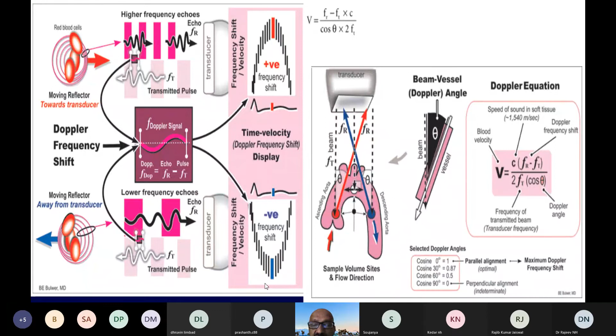Coming to continuous wave Doppler, now we'll go into the 4 different types. First one is the continuous wave Doppler. In the continuous wave Doppler, there are 2 transducers, two piezoelectric crystals. One is continuously emitting the ultrasound waves, one is continuously receiving the ultrasound waves. When you activate the continuous wave Doppler button on the machine, you will be activating 2 crystals, one which is emitting the rays, the other one is receiving the ultrasound waves.